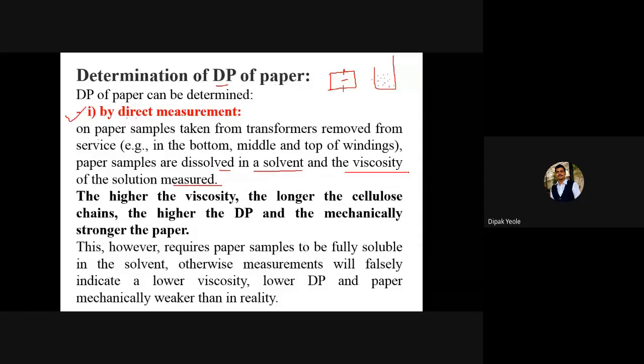So we have to measure the viscosity. The higher the viscosity, the longer the cellulose chain. We know the paper is made up of cellulose chains. So if the value of viscosity is higher, it means longer cellulose chain and higher DP. So there is a direct relation. After measuring the viscosity, a longer cellulose chain results in a higher amount of DP, and we know that if the DP is higher, the paper is mechanically stronger.